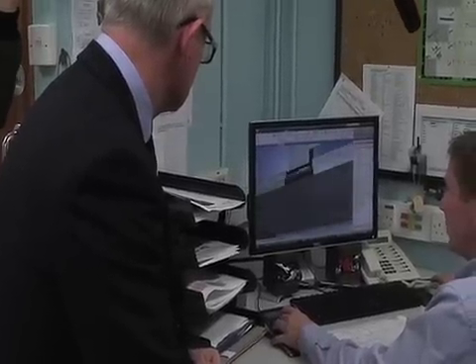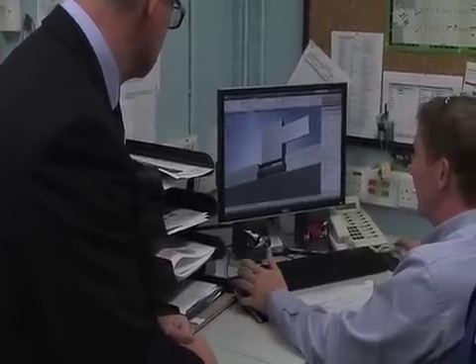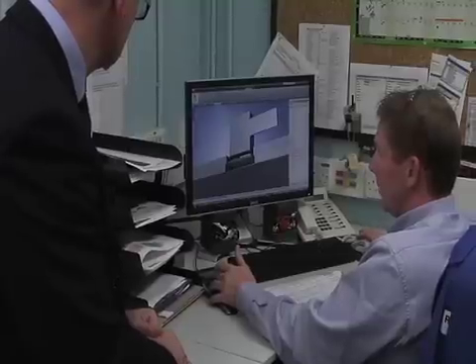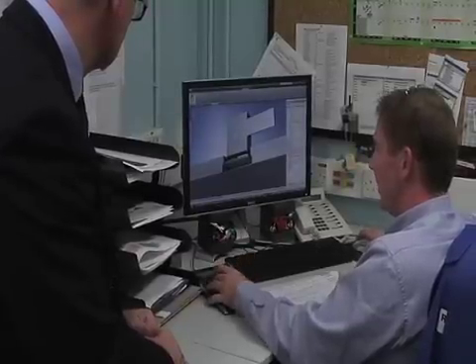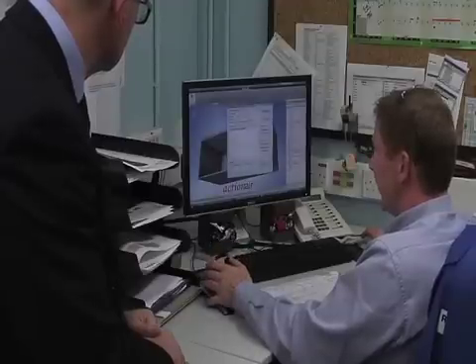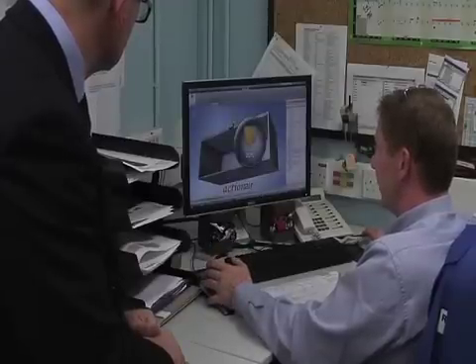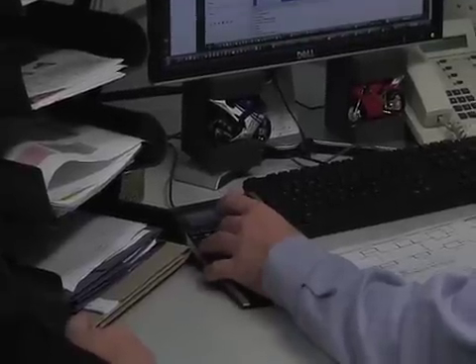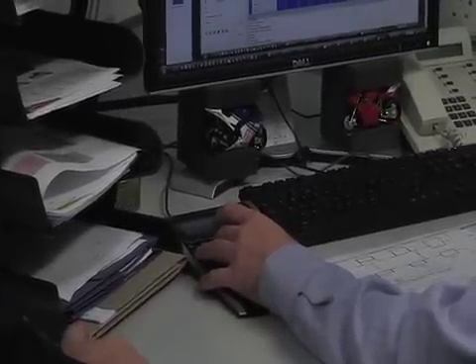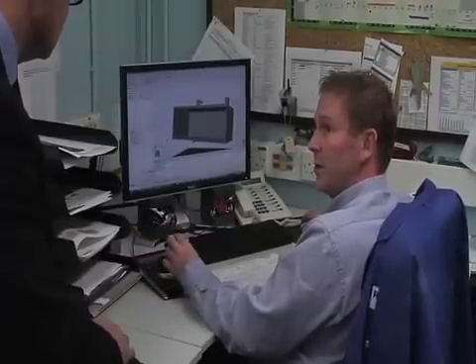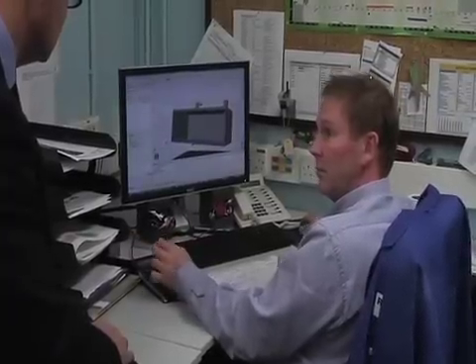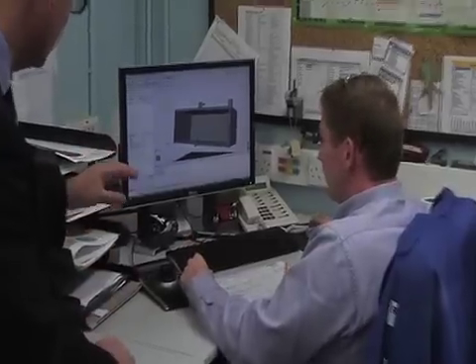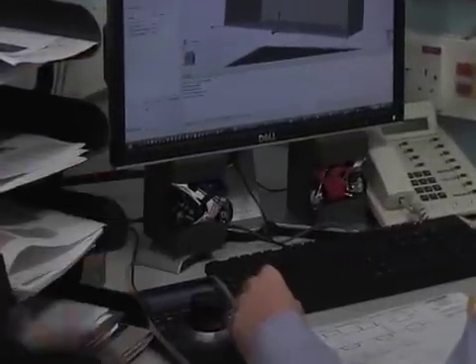We can take it straight into a program called CF Design, which is integrated with Inventor, and take it through some of the computer flow dynamics. We use it to replicate some of the Coanda effects that our grills and diffusers are throwing out with different air pressures and air velocities. We've got an example of one that we've done to show what it looks like from an air flow point of view.